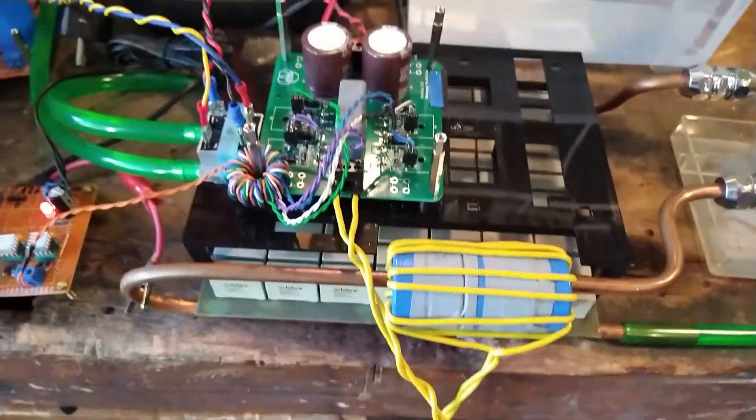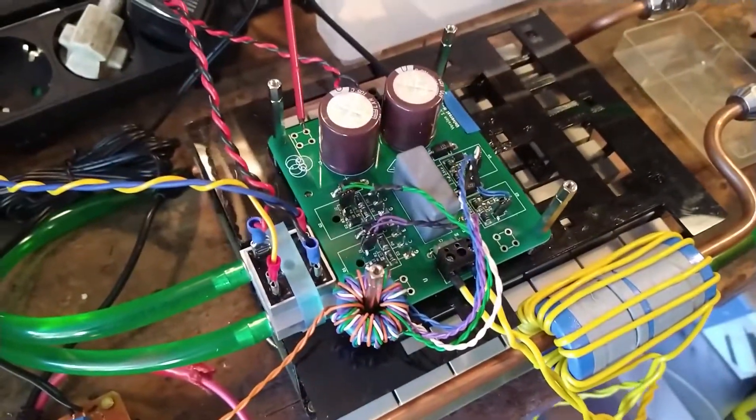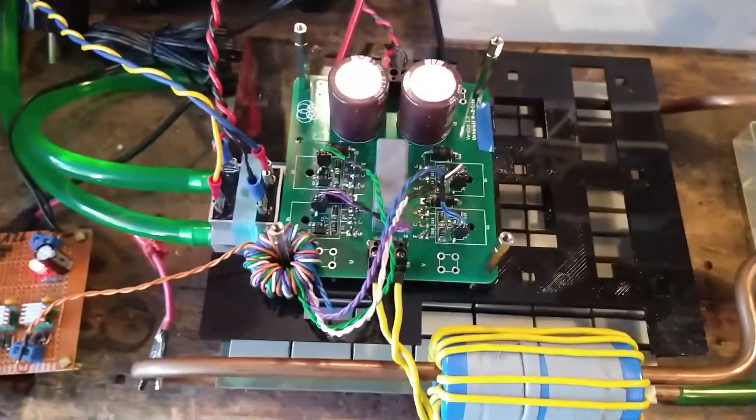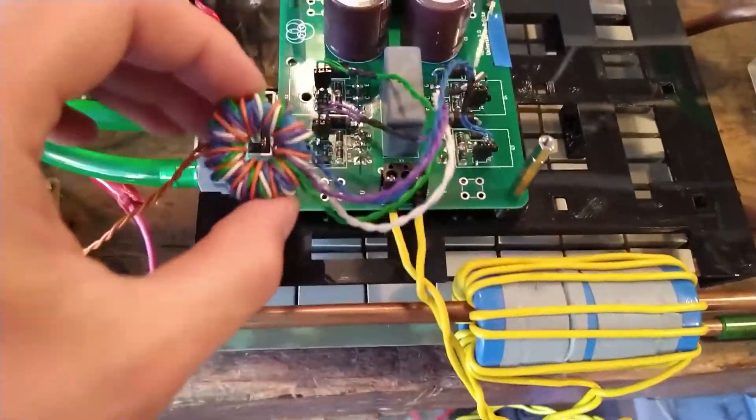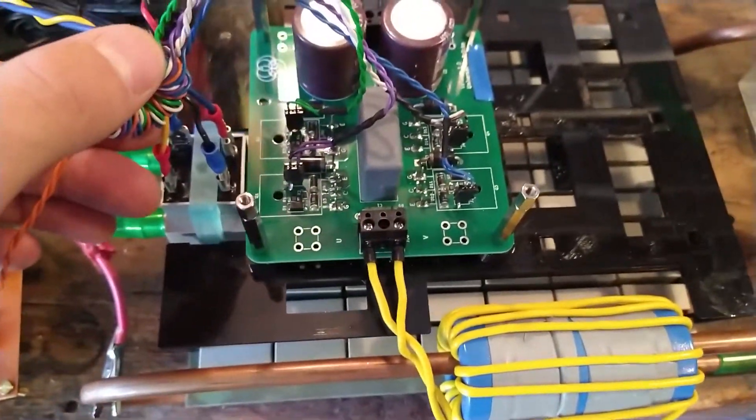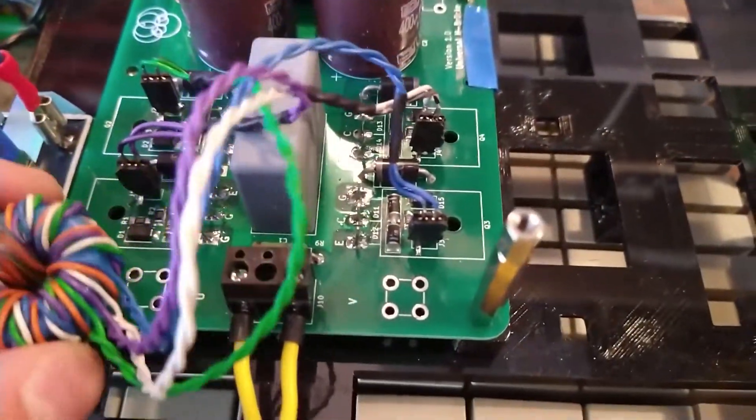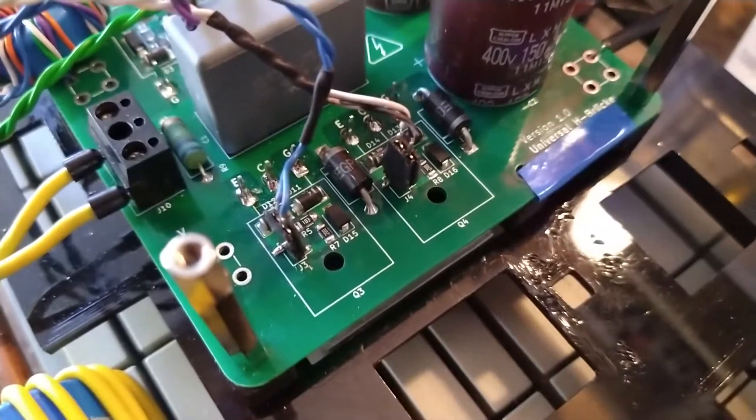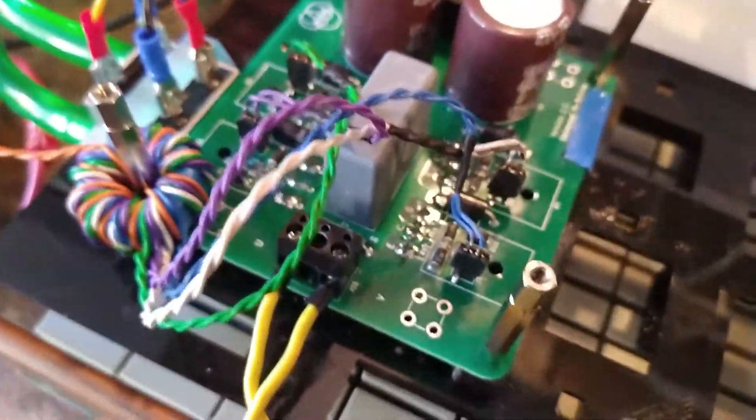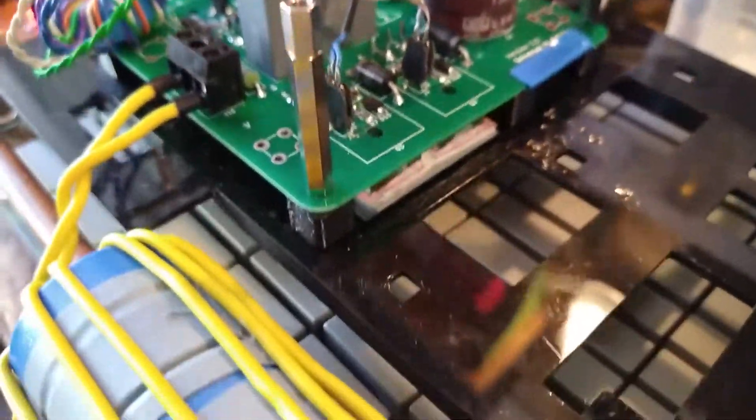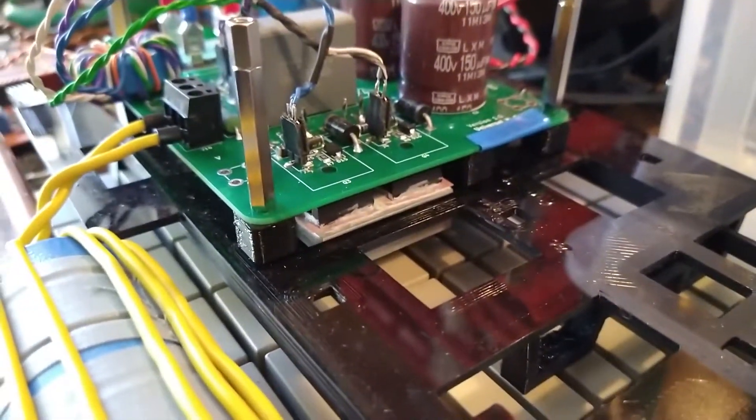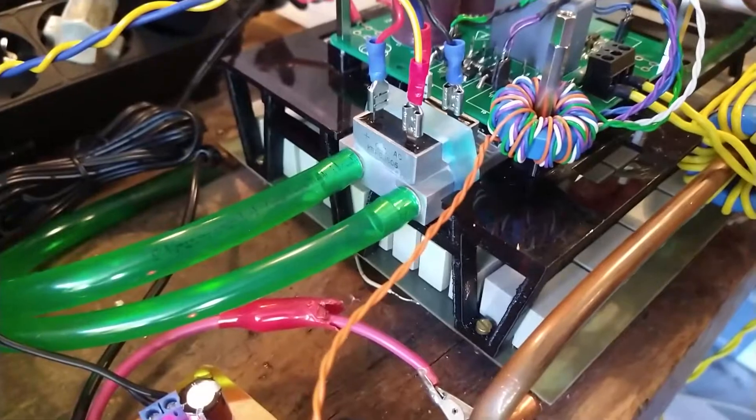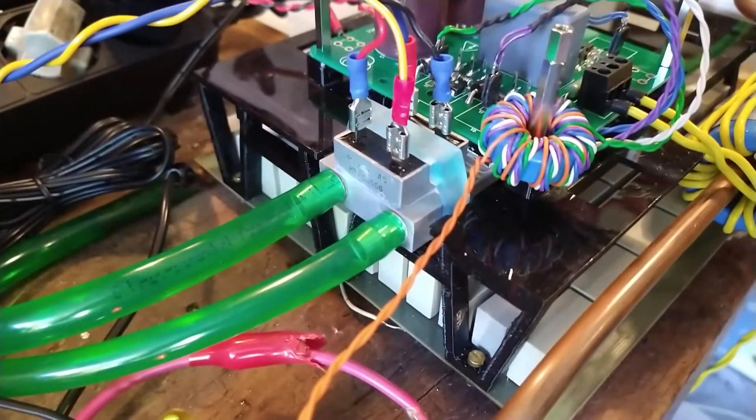It's driven by this transformer that's fed by an inverter, this is an H-bridge inverter that can be fed by mains power. The gate signal comes over the gate-drive transformer here, feeds into the protection circuit for each IGBT. The whole PCB is a low-inductance design and the IGBTs themselves sit underneath the PCB on a water-cooling block made of aluminium.